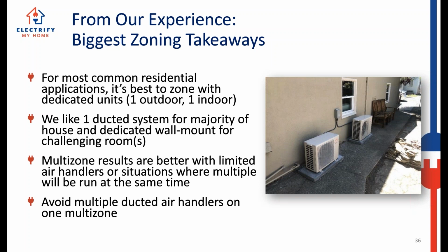But what we don't want to do, and I had a peer of ours that also installs heat pumps that I was chatting with a couple of weeks ago, and they are taking the communicating modulating system. They're putting a low voltage or a traditional thermostat interface module and controlling the unit with that. And then they're running a zone control system through that interface module. So they're cutting the efficiency off at the legs on the system itself. And then they're running all of these regular analog thermostats and trying to make it work on this equipment.